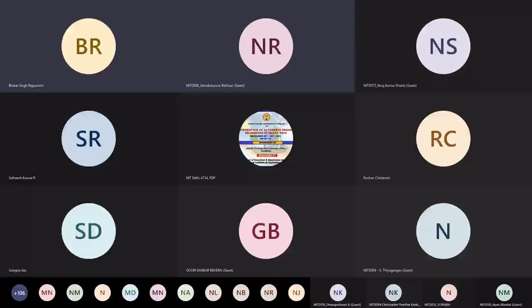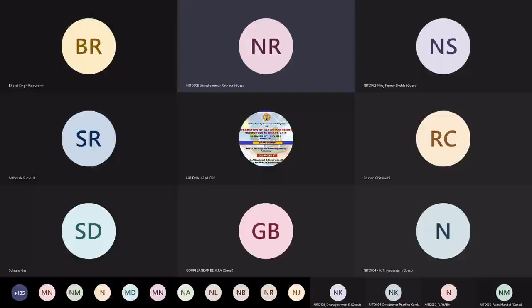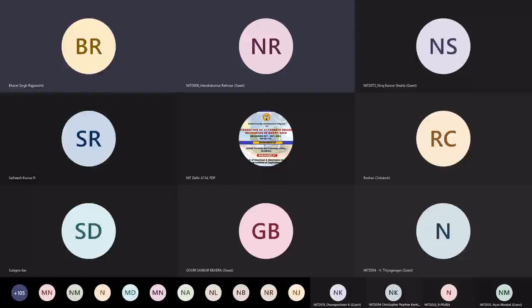Okay, sir, but actually mostly wind power plants are isolated and there are no manual operations. So this can be done automatically by SCADA control. Yes, it can be done by automatic SCADA control, and it is done by automatic control. A manual operator is generally not required unless some emergency situation is there. So it is already programmed, and these curves are fed in, and whenever some signal comes from the load dispatch centers that you need to back down, the reference set point is reduced, so that the set points of each individual wind turbine are reduced, and the power can be backed down. Okay, thank you, sir. Thank you very much. Thank you.